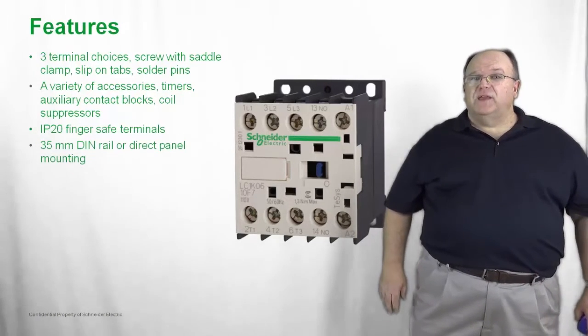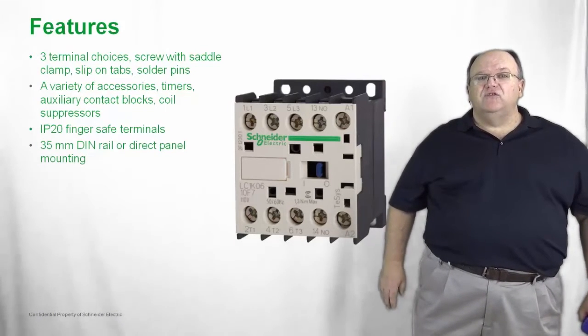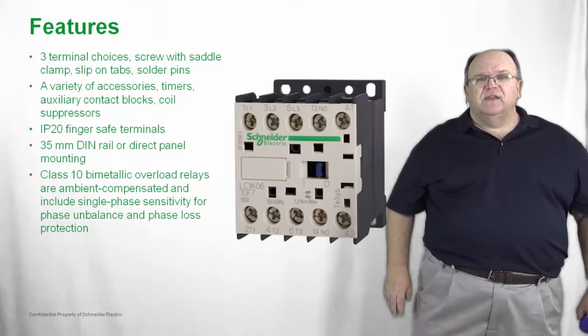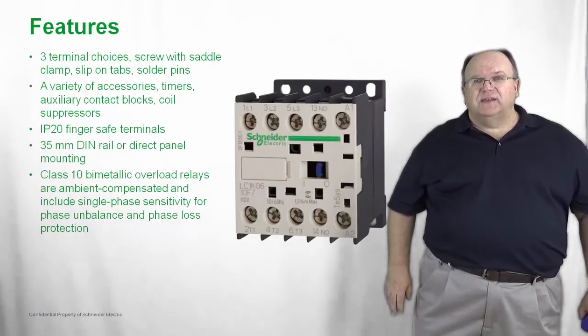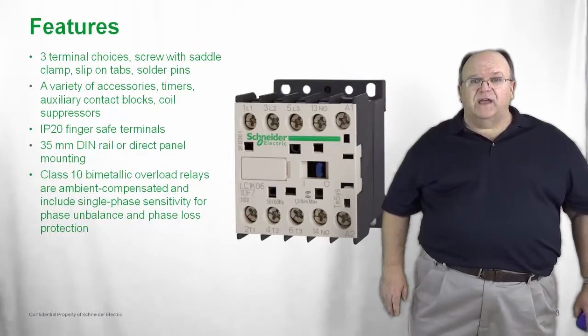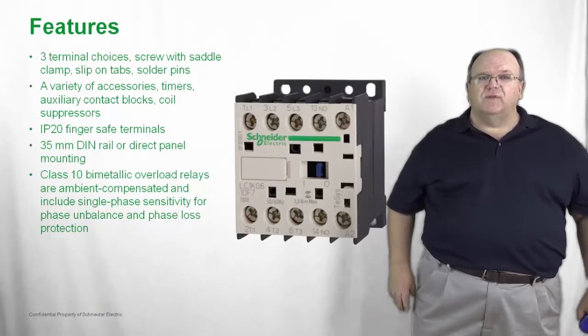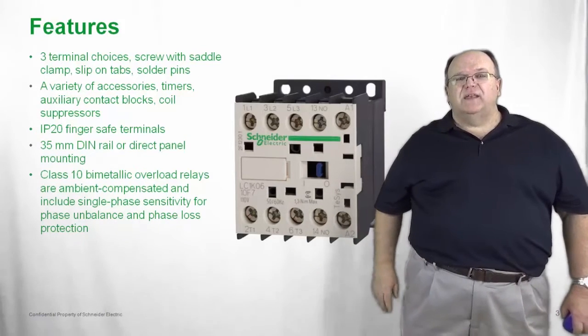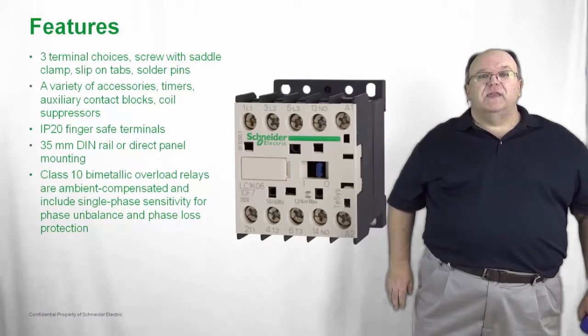The product is available for either panel mounting or 35mm DIN rail mounting into any control panel. The overload relay supplied with the TeSys K is a Class 10 bi-metallic overload that is ambient compensated, meaning it can be used indoors or outdoors where temperature varies. It also includes phase sensitivity, so if you have an unbalanced load or single phase loss, the overload relay will trip and safely protect the motor.